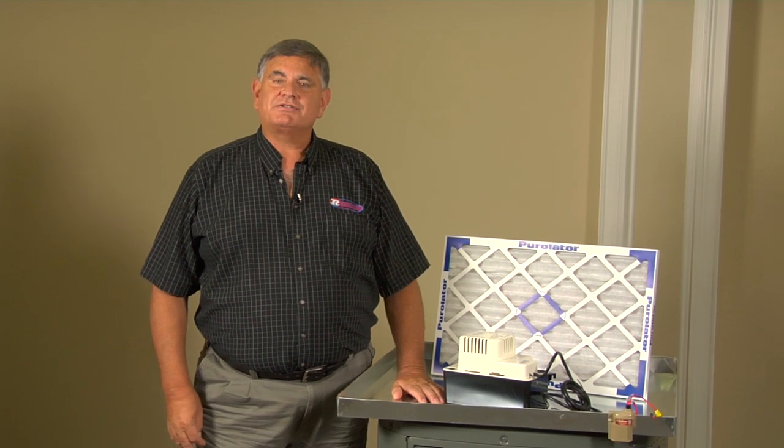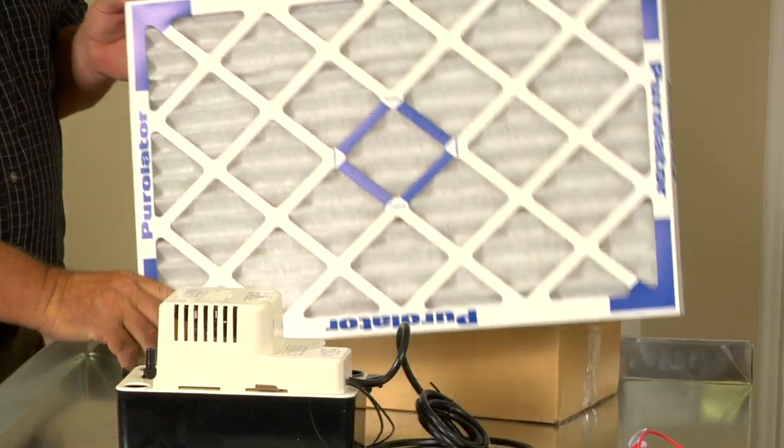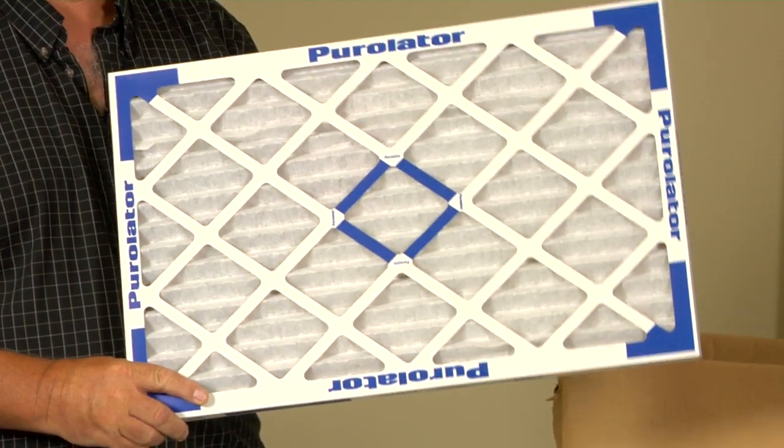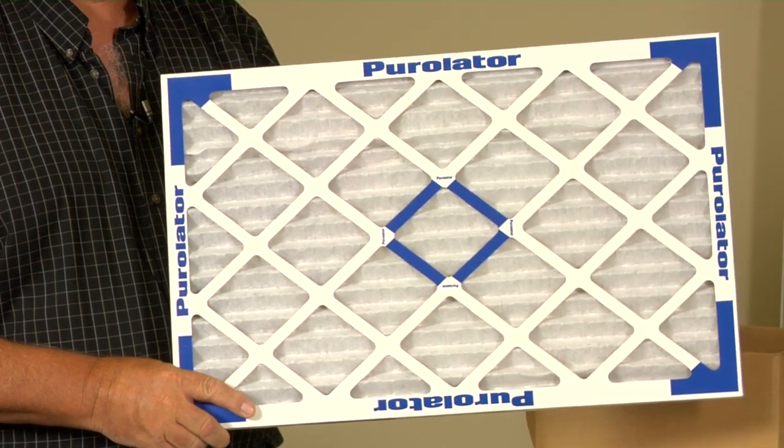So if you come home and you don't have any air conditioning, there's a few basic things you can check. First, what you want to do is go down and make sure that your filter's clean. Oftentimes a dirty filter will stop cooling, it can actually cause an ice up. So check your filter.